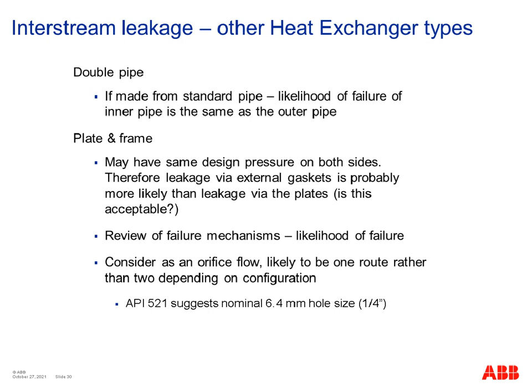Right. So going on to interstream leakage for other heat exchanger types other than shell and tubes. Obviously there are other types of heat exchangers, so we need to think about that event in those cases. So for a double pipe heat exchanger, the tube failure case isn't normally considered, and that's because you think about the inner pipe or the inner tube of the exchanger is really just the same as a standard pipe on the plant, and the likelihood of it failing is as high or as low as the outer pipe would be failing anywhere else on the plant.